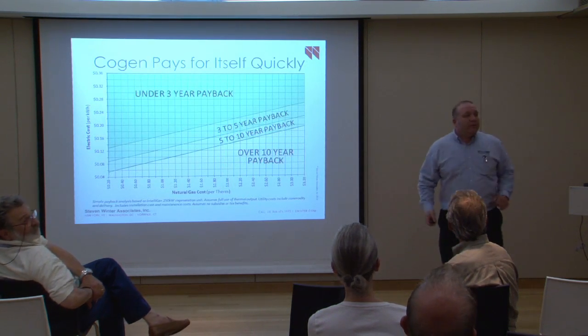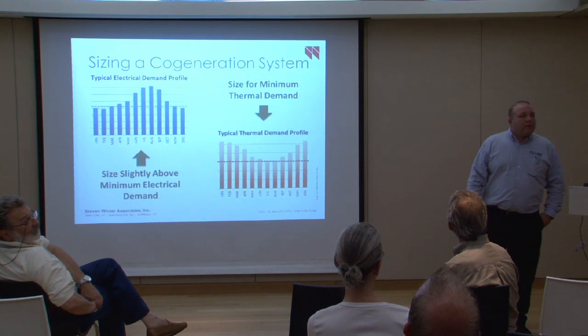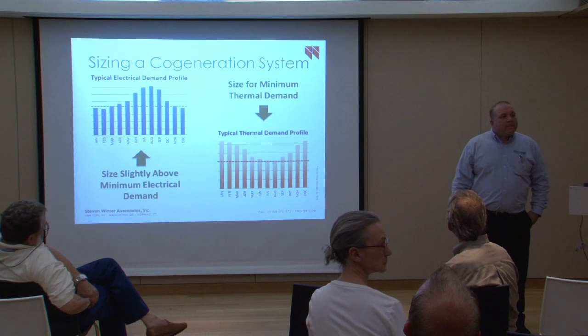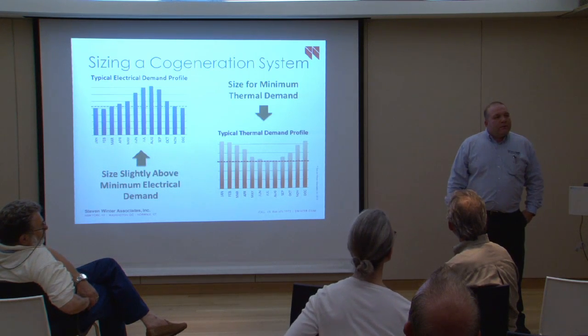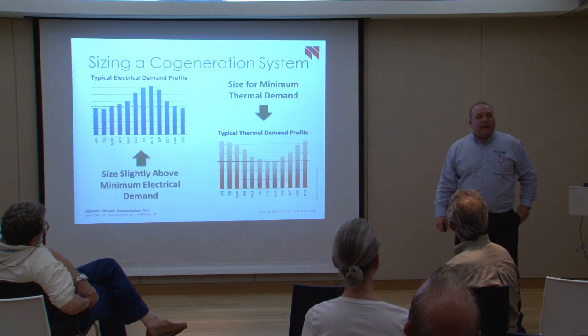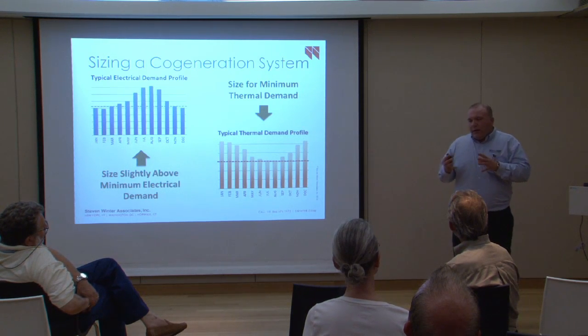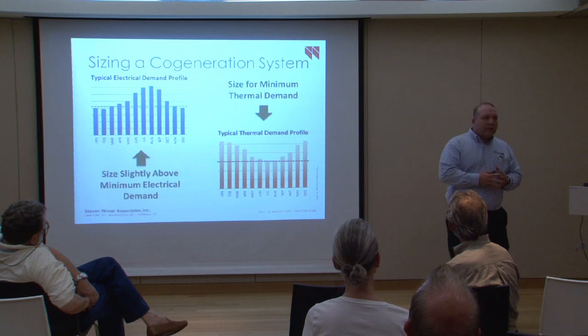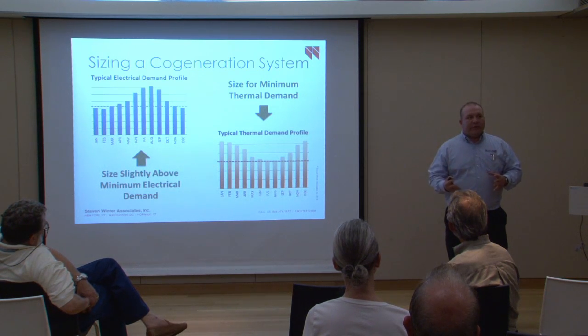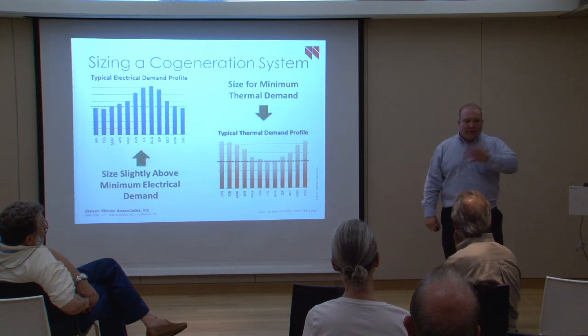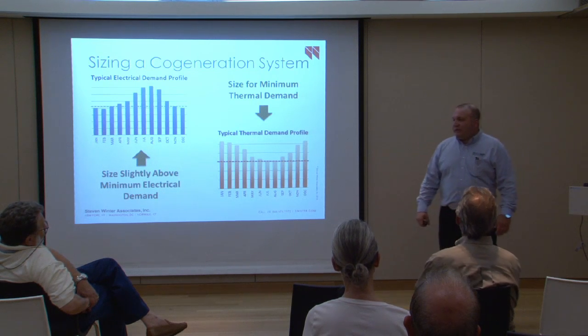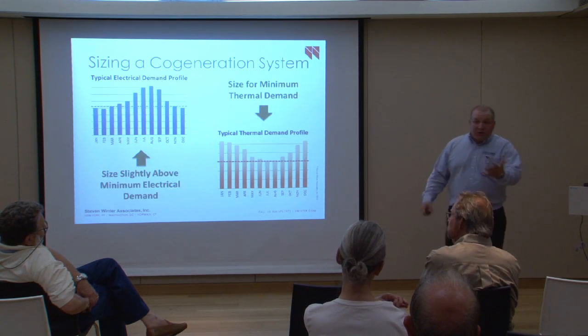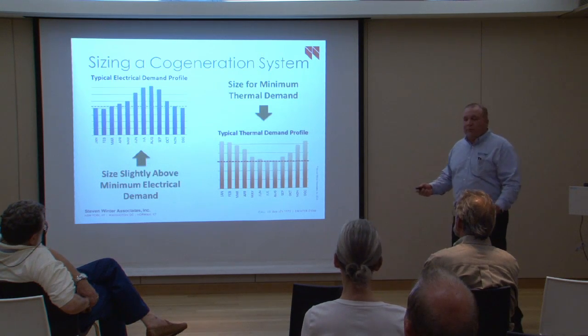Is there a scenario for catastrophic failure, where you can't connect and have to stand by yourself? The systems we're designing today, which will be part of this microgrid, are standalone. They're designed to run in parallel with the grid, but also act as emergency power systems if the utility fails. That dual-purpose design drives pretty much everything we do. The 2003 Northeast blackout made a lot of people realize that resiliency matters alongside energy efficiency, and that combination is really what cogeneration lends itself to.